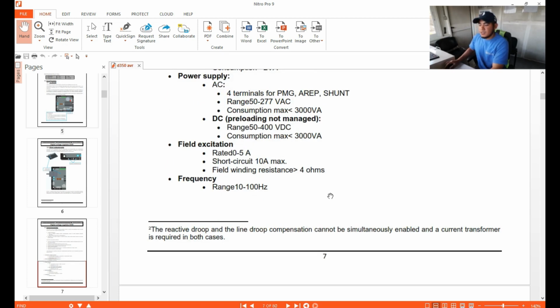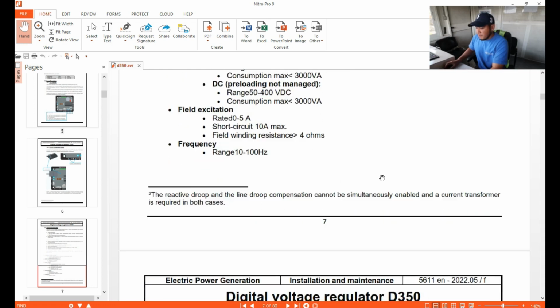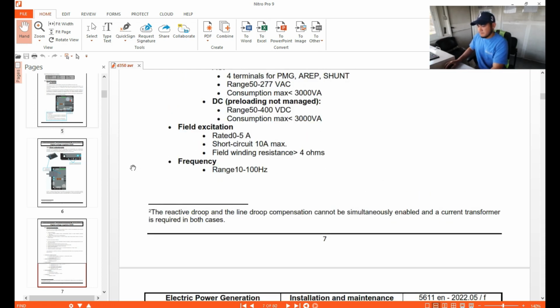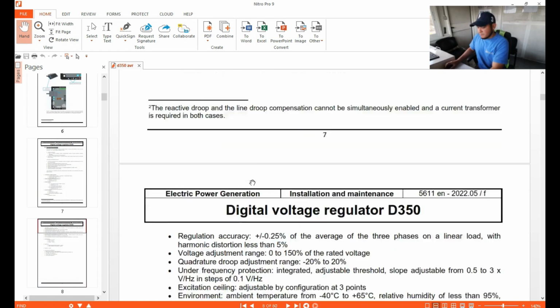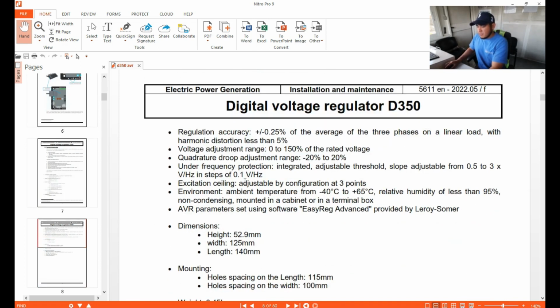The field excitation is rated 0 to 5 amperes, and the maximum short circuit is 5 amps. The field winding resistance is 4 ohms. Frequency ranges from 10 to 100 hertz. Let's continue. The regulation accuracy is plus or minus 0.25% of the average 3-phase on a linear load, with harmonic distortion of less than 5%. Voltage adjustment ranges from 0 to 150% of the rated voltage.